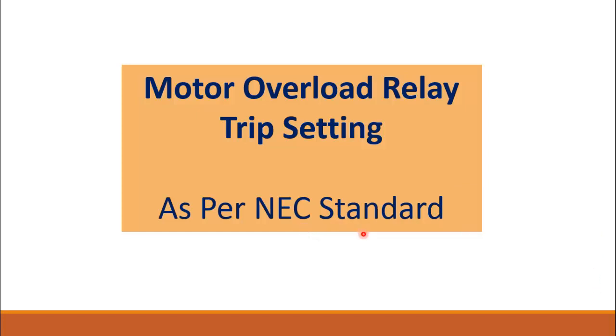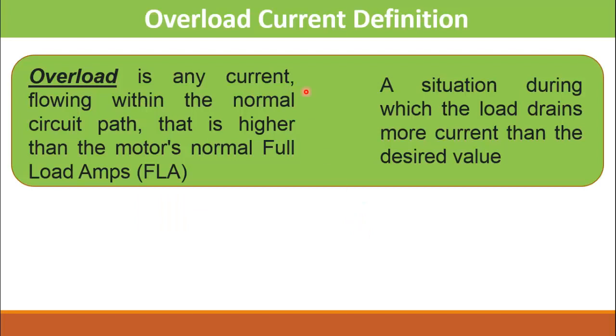First, let us see the definition of overload current. Overload current is any current flowing in the circuit which is higher than the motor's normal full load current. This means the load driven by the motor is more than its power rating, or there is some abnormality causing the motor to draw more current than rated. This overload current is a slow process and is dangerous for the life of the motor as well as the whole circuit.